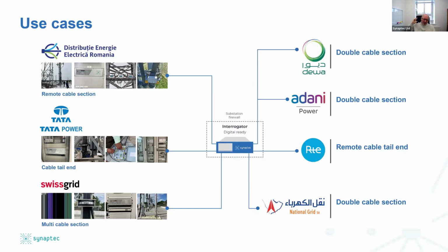Or you've got examples of cable systems in the middle of the desert where there is no access to power supplies. You can't build a substation out there, and there's no way to link the communications back. There's simply no communications infrastructure to make use of. So most of these examples are situations where the circuit is traversing challenging domains and geographies where it's very difficult to install conventional systems, and so the operator simply didn't. And if they make that choice, that's okay, but clearly you're taking a risk because the protection scheme might not operate properly if the fault's in the cable section. So this system delivers that reassurance and rapid response in a scenario where you've got that remoteness or inaccessibility, you can't have access to telecoms at that location, or you simply don't want the cost of building another substation to host all of that infrastructure. I think these are all interesting ideas.